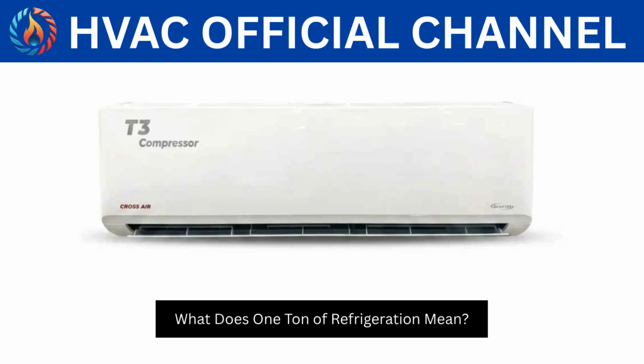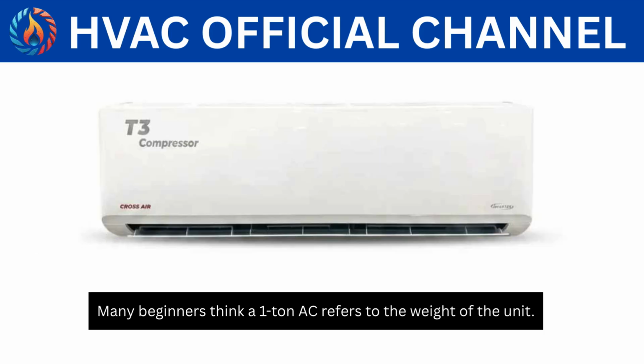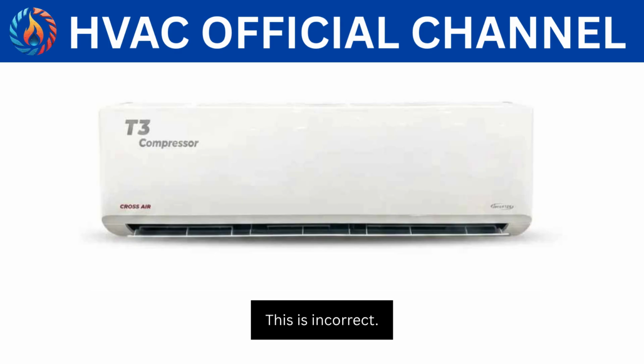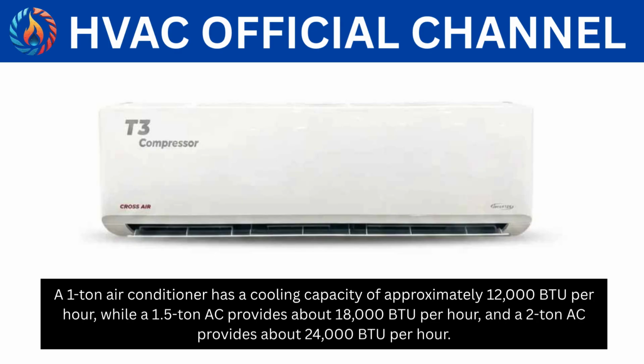What does 1 ton of refrigeration mean? Many beginners think a 1 ton AC refers to the weight of the unit. This is incorrect. A 1 ton air conditioner has a cooling capacity of approximately 12,000 British thermal units per hour, while a 1.5 ton AC provides about 18,000 British thermal units per hour, and a 2 ton AC provides about 24,000 British thermal units per hour.